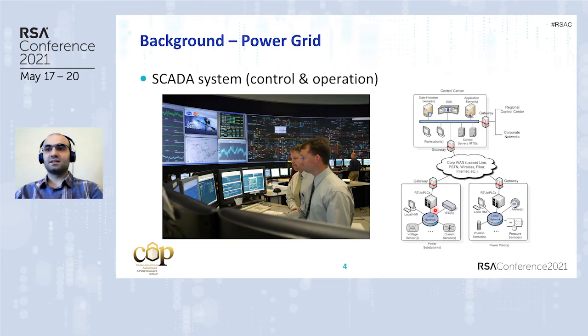The monitoring devices, such as voltage sensors and current sensors, poll the measurements in these substations and return the readings to the control center. The control center processes this information, and using automated tools or human operators, decides on control actions to be implemented in the substations. These control actions could be switching circuit breakers, changing the system configuration, or increasing or decreasing the power generated by different power plants to meet new grid requirements.